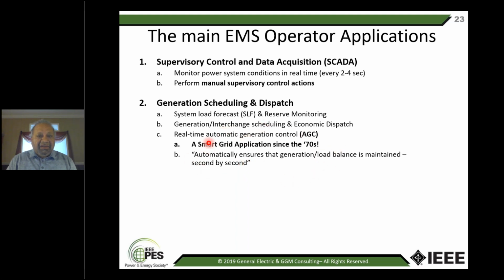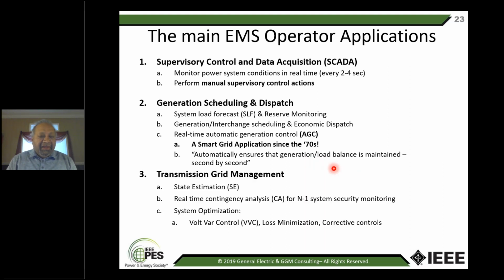This is the only closed-loop function in the control center, meaning it acts like an assistant to the operator, sensing generation-load imbalance and immediately sending controls to the generators to bring it back to balance. Then we have the transmission grid management system: state estimation, contingency analysis, security analysis and optimization, volt-var control, and loss minimization.